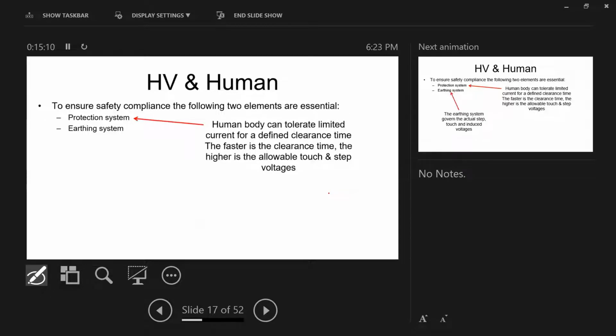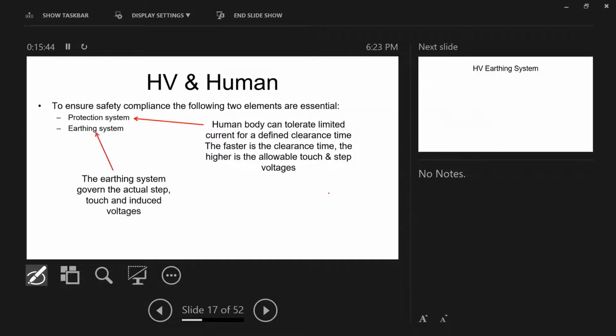Now, for us to have a protection system, you will see later on, that the time required for the current to trip and isolate also depends on your earthing system. So even for a protection that gives you a reliable network, if you don't have a proper earthing system, your protection time will go up. If your protection time, the clearance time, goes up, you are jeopardizing the safety of everyone around you. The resistance of your earthing system governs the actual step and touch voltages. So there is an allowable limit that will be governed by the human body, the clearance time and the soil resistivity.